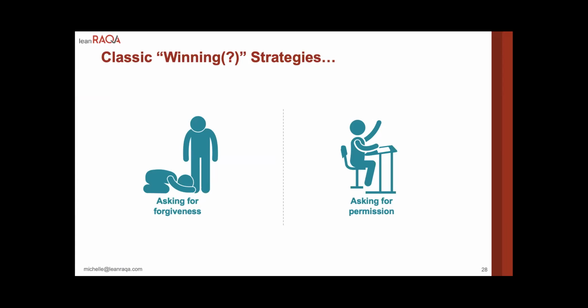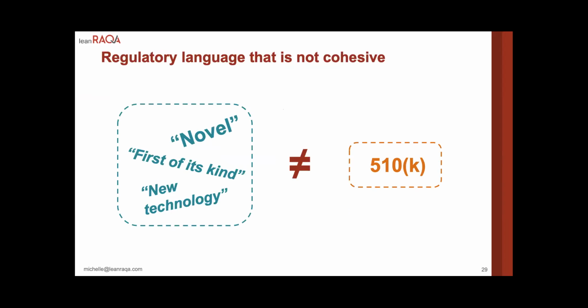So I have found that it's much better to ask for permission rather than forgiveness with the FDA. In pitch decks, be on the lookout for regulatory language that's not cohesive with a regulatory strategy. If you hear the words novel, new, first of its kind, those things are not equivalent to 510K. If a company's saying, hey, we're class 2 510K, it's going to be a straightforward regulatory path, and then they're also rattling off this new novel technology features, those are a de novo, which literally means of new, and that you won't have a predicate for those things. So the 510K relies on you having a predicate where you claim substantial equivalence.